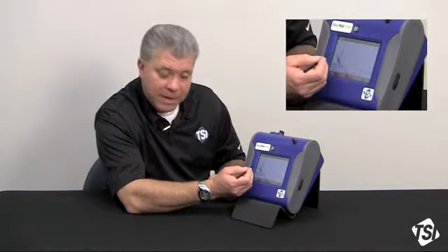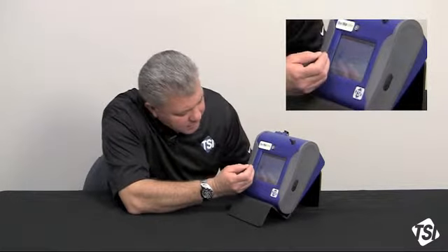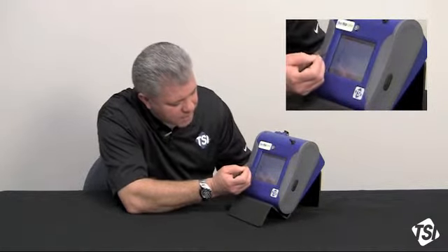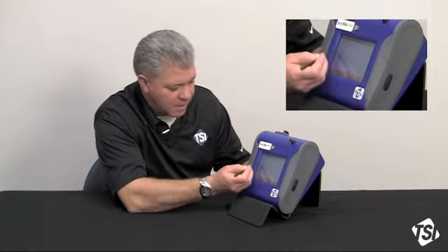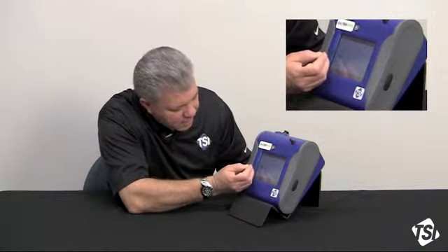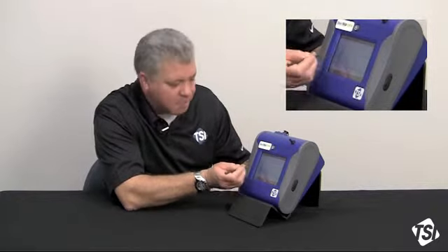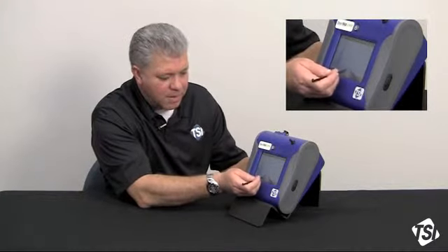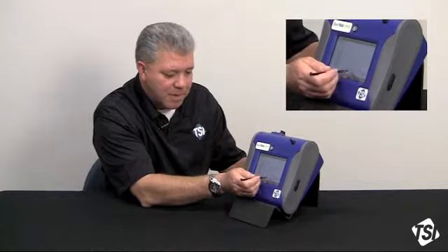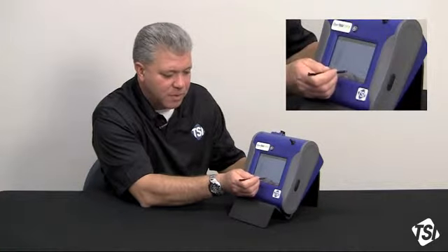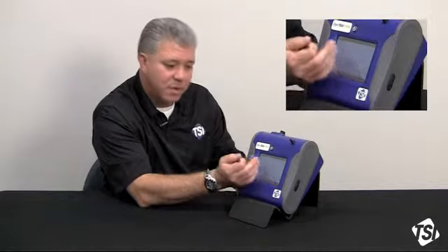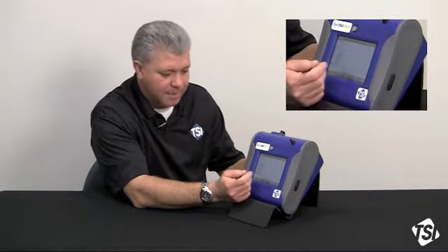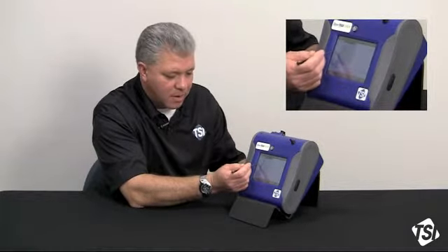Over in the y-axis, right now we've got total being displayed. I can touch over here in the y-axis and change the size fraction. Now I have PM10. Now I've got respirable. I've got PM2.5 and PM1. You can actually see the screen changing. Down at the bottom over here under time, I can change my timing conventions from relative to actual and so on and so forth. It's just how you want to perceive and look at your data on the x-axis. But it is really a nice tool to be able to toggle over on the y-axis.